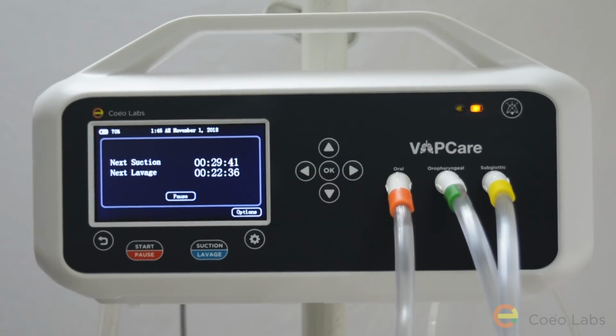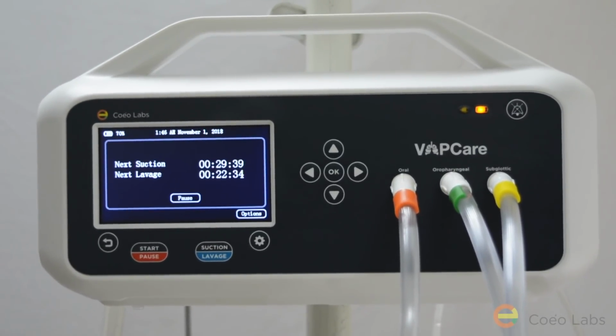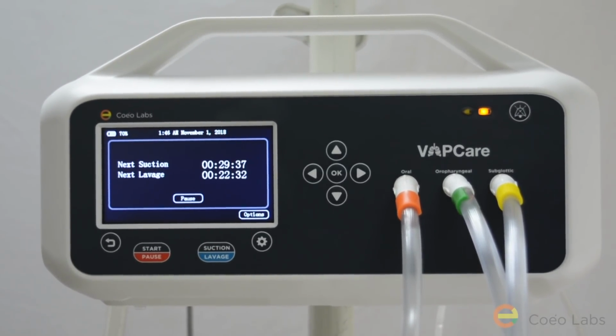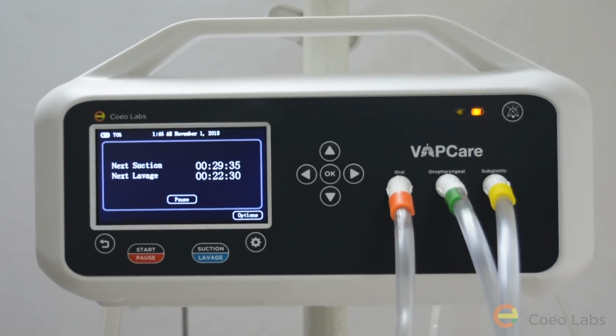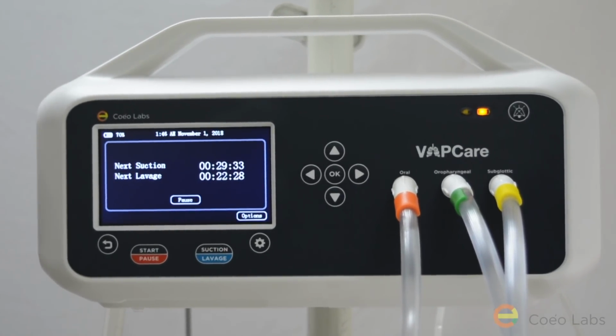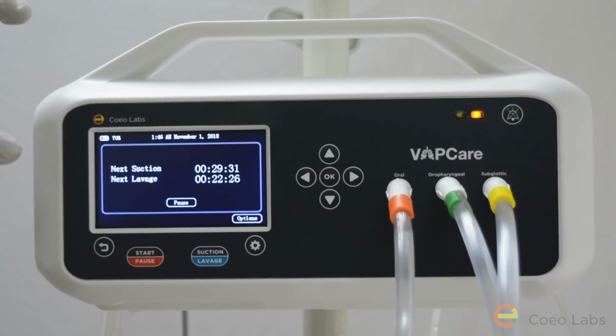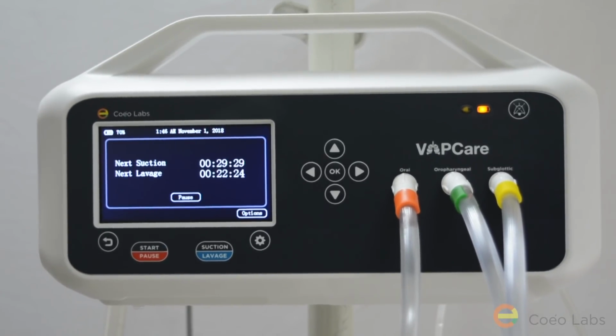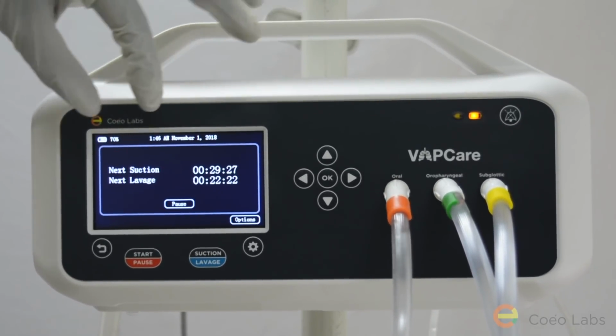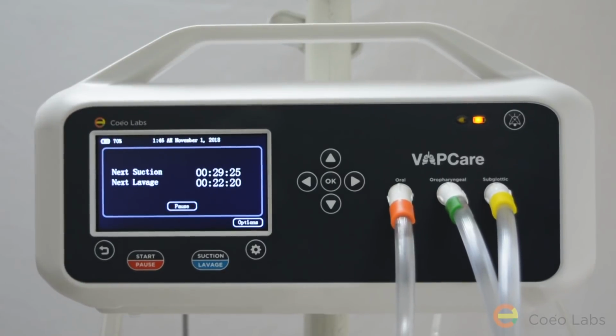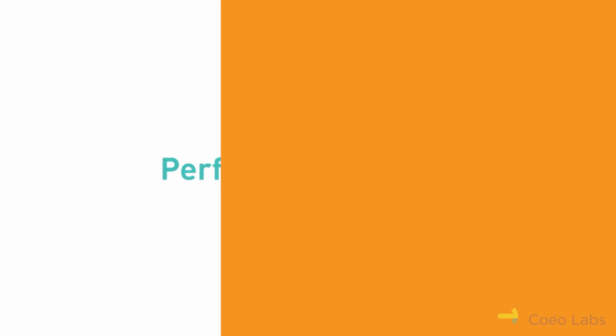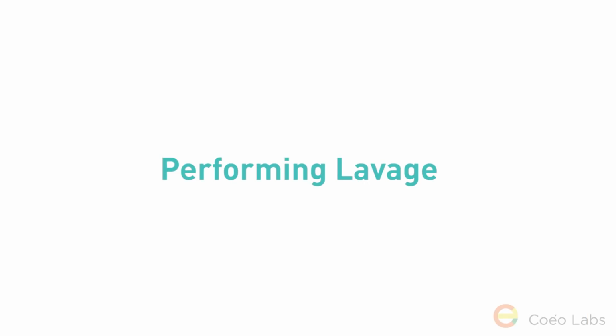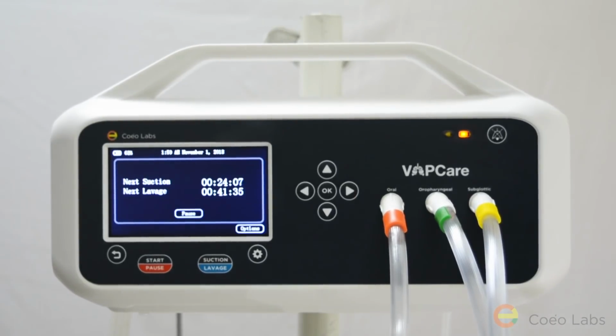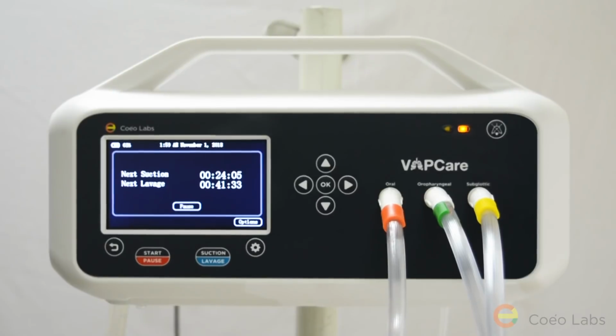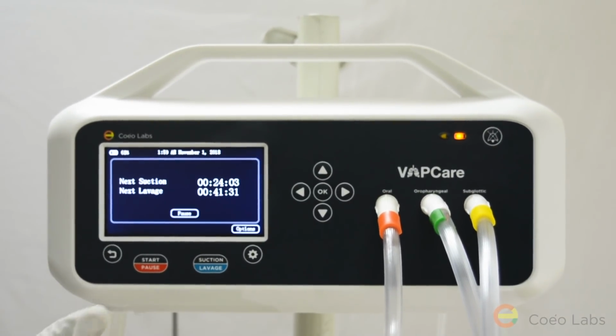The suction cycles continue as oral, followed by oropharyngeal, then by subglottic. At the end of all the 3 cycles, the device goes into an idle state. On the screen, it mentions the next time of suctioning and the next lavage timing. The device has on-demand suction and lavage feature in addition to the routine cycles.